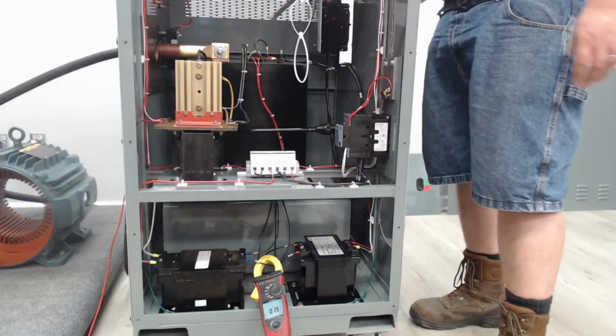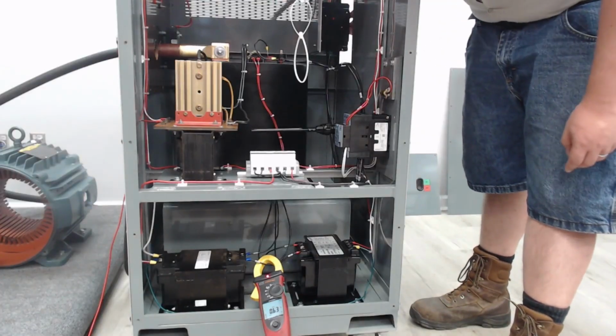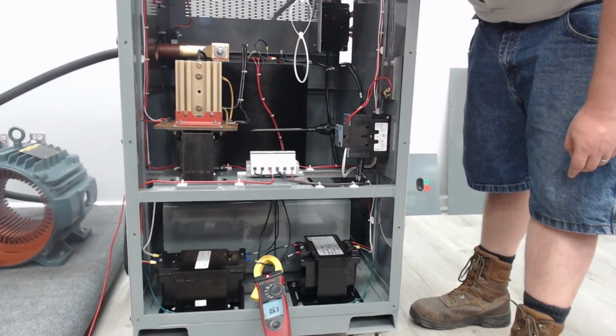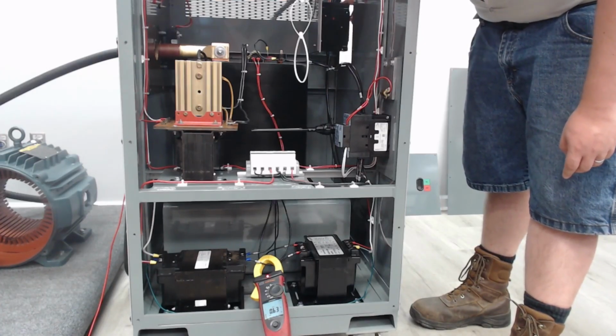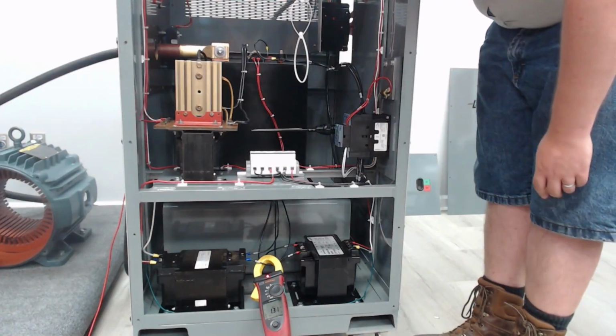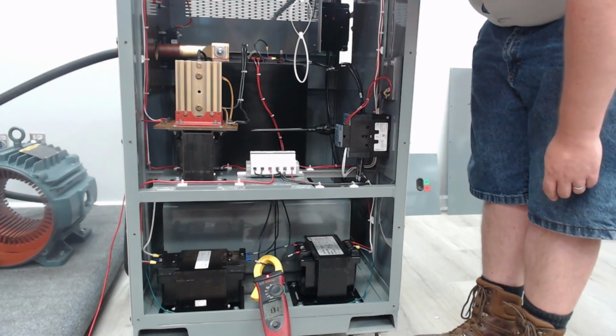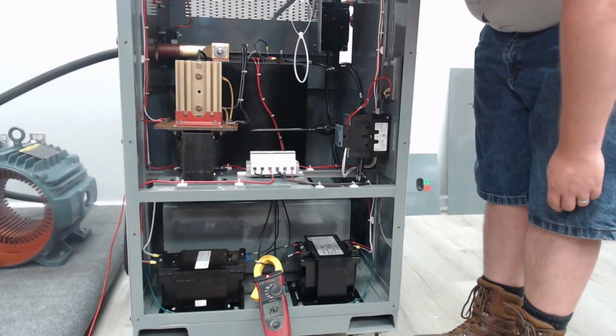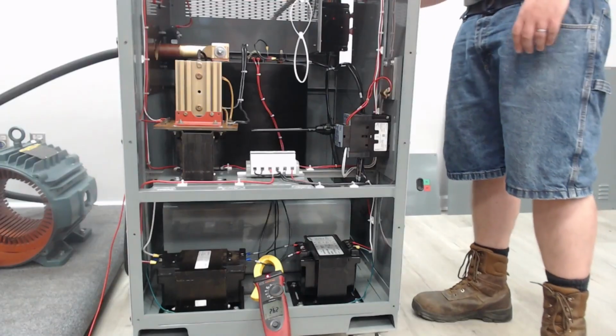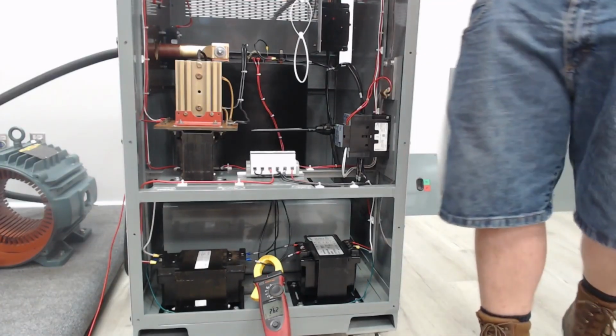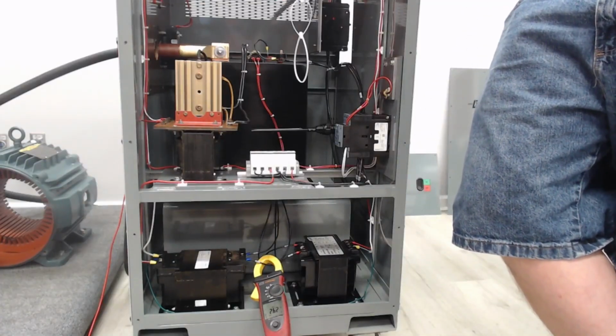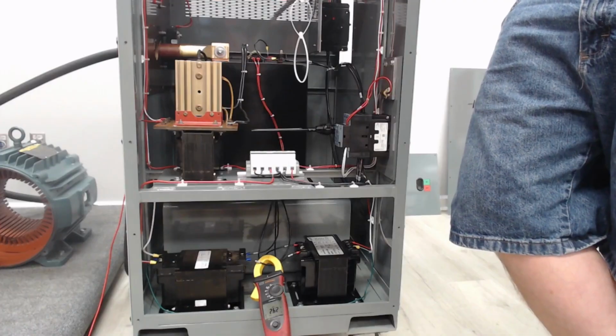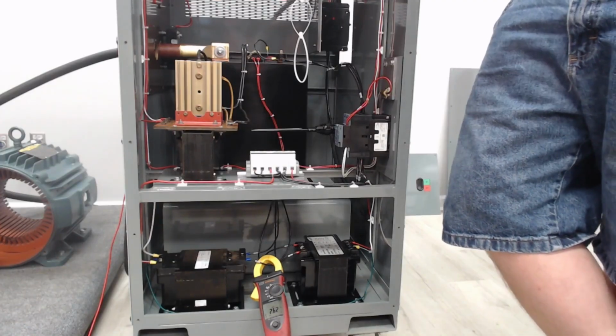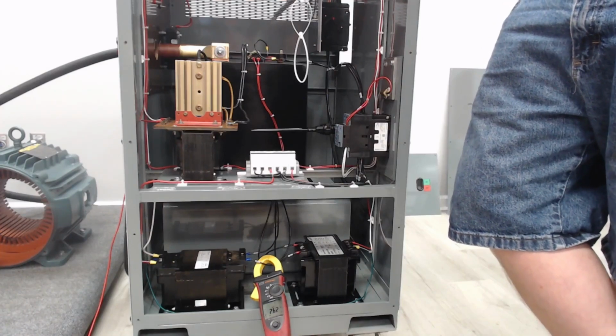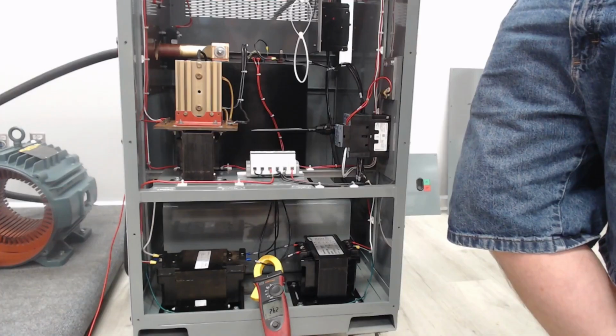All right, 6.3. 1.3, 2.65. All right, yeah. So I think for a 2 amp fuse, we did exceed it there, and that's going to be the inrush. That should be a time delay, should last very well. You should have no issues with that. But if you're jumping up to 4 or 5 amps, then that's going to be where your inrush problem comes from.